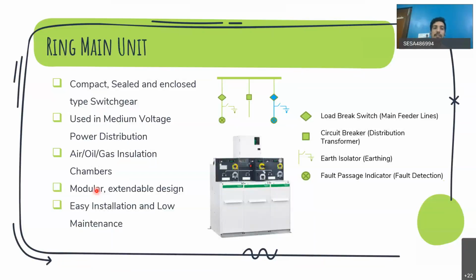So what is that equipment? That is nothing but a ring main unit, or RMU. RMU is also a type of switchgear which is compact, sealed and enclosed in nature, so it is not very bulky in size. Generally it is used in medium voltage networks, that is 11 kV, 6.6 kV, etc., based on the country. Another big advantage is that it has all this protection equipment. It has air or oil or gas insulation chambers. And the main advantage of this is that it is modular and extendable in design.